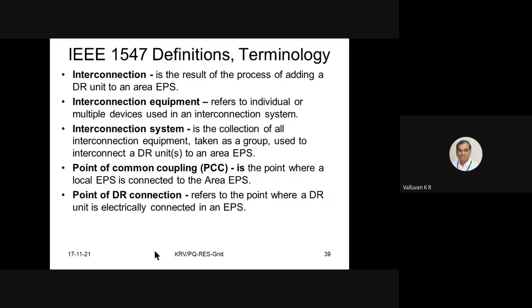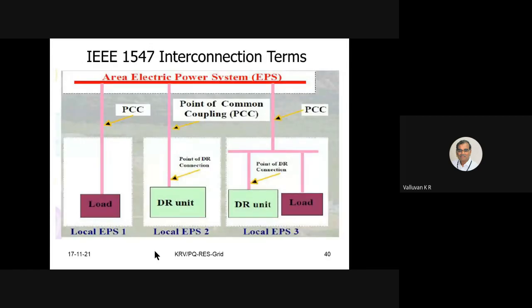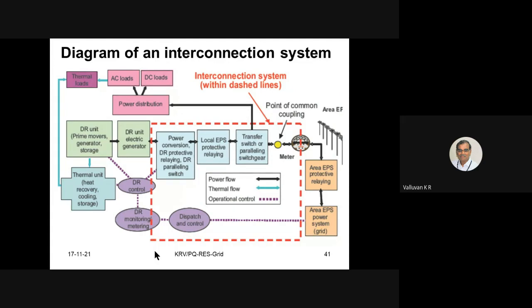Point of common coupling is one term which we have to be very, very aware of. It is the point where the local EPS is connected to the area EPS. Point of DR connection refers to the point where a distributed resource unit is electrically connected to an EPS. All these terms are explained in this diagram. At the bottom, you have loads and DR, distributed resource units, several distributed units and several loads, connected through the PCC to the area electric power system, which goes to the national grid. This diagram shows how the distributed resource units are connected to the grid, how the local EPS is connected to the area EPS, and how the area EPS is connected to the national EPS.